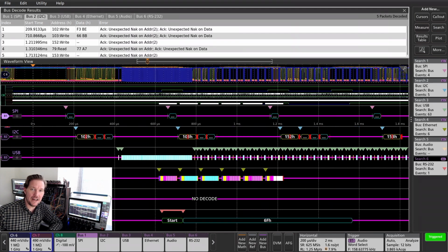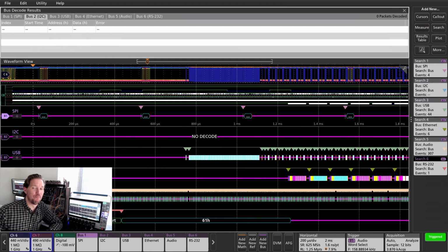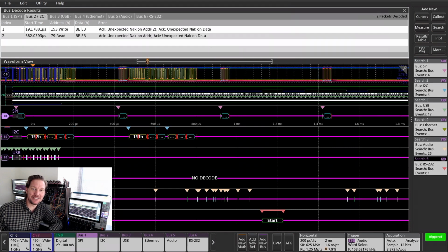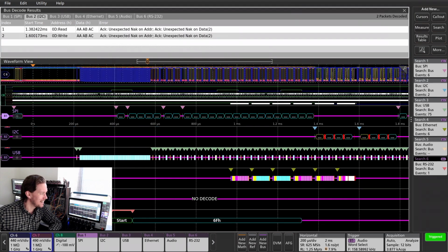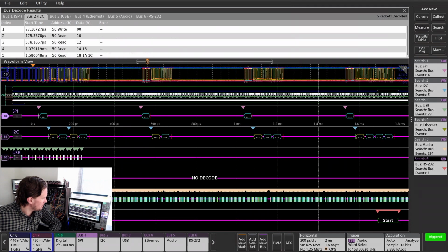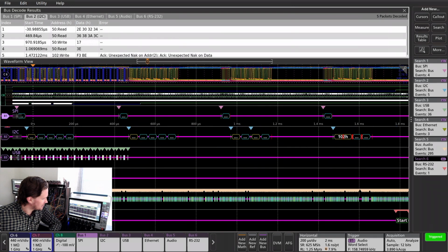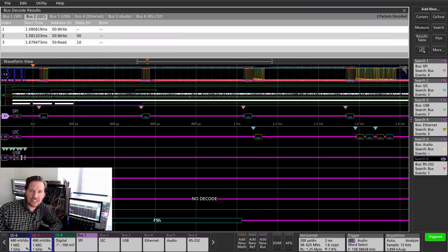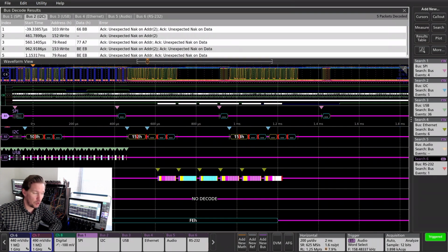Hello, in this video I answer the question, how many buses can I analyze simultaneously on an MSO 58? The answer is basically how many channels do you have? I had, let's see, 7 passive probes and 1 8-channel digital probe at my disposal.